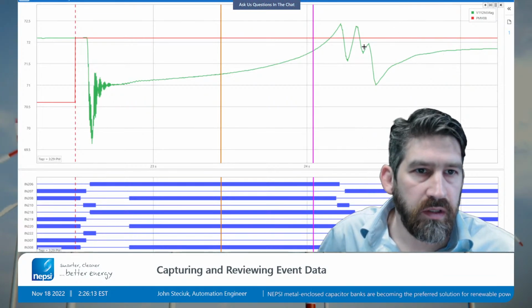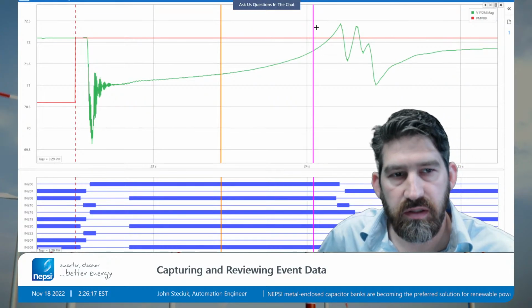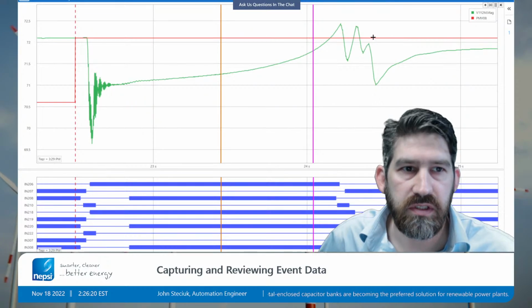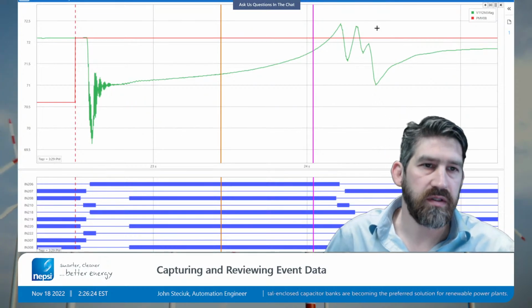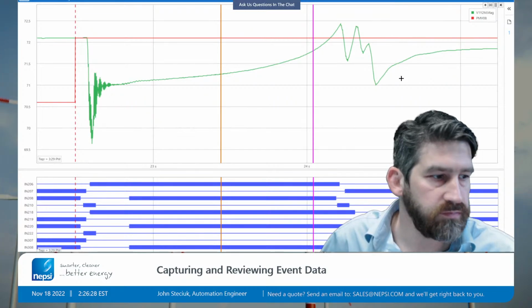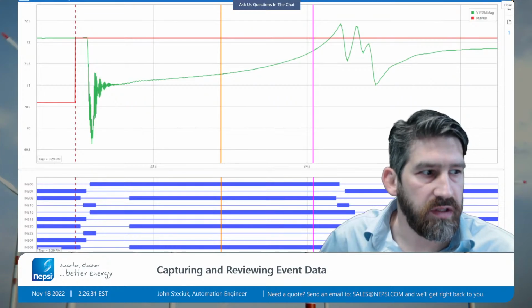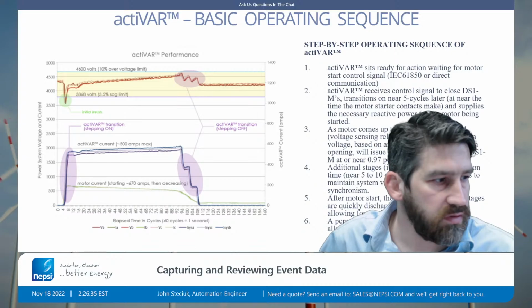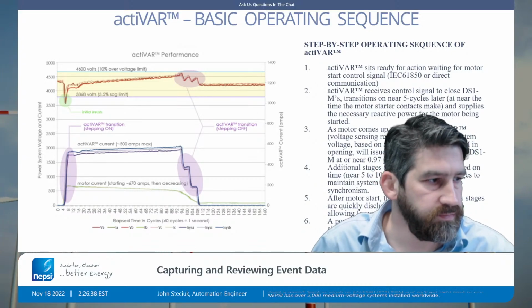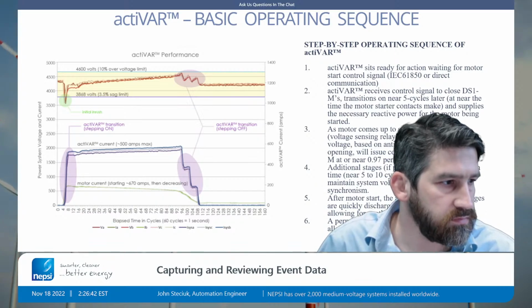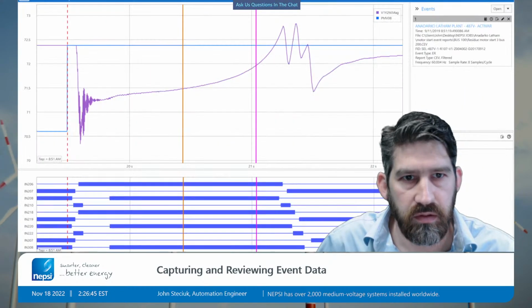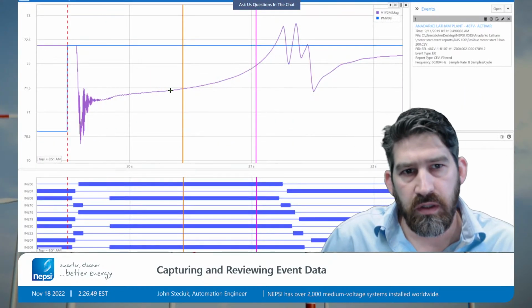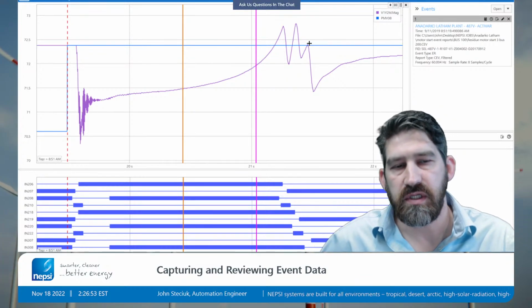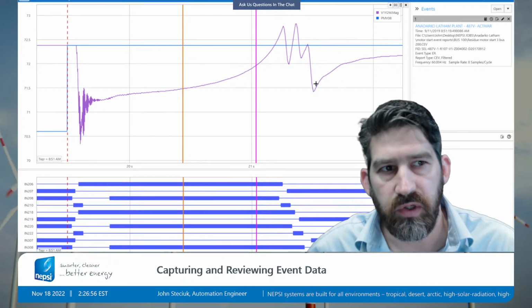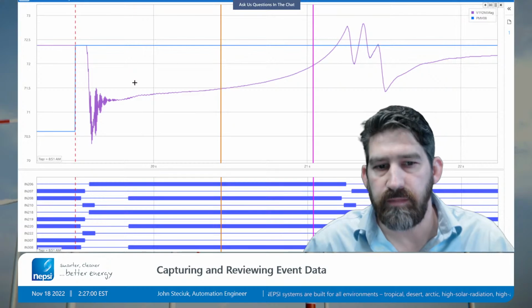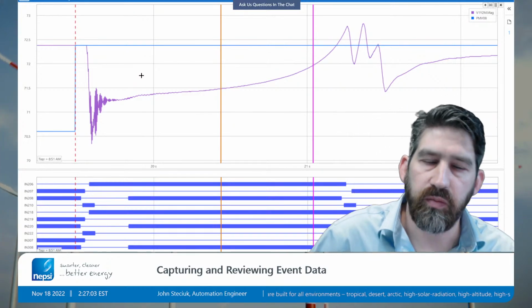So then what we wanted to do on this one was to adjust the timing on the back end to allow the voltage to slightly overshoot on the tail end. So we made our adjustments with the timing and the logic, and took another event report. And here's the results of that. We delayed a little bit longer to shut off the third stage of capacitance, and got better results for the customer. So another useful application for event reporting.